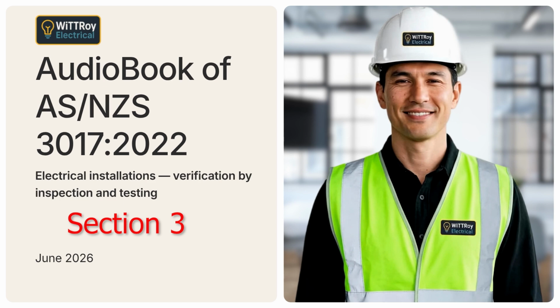The connection of wiring must be checked. Protection against external influences must be checked. The arrangement of the consumer mains must also be checked. In simple terms, consumer mains are important because they are close to the supply side of the installation, so identification, protection, connection, and arrangement must be correct.